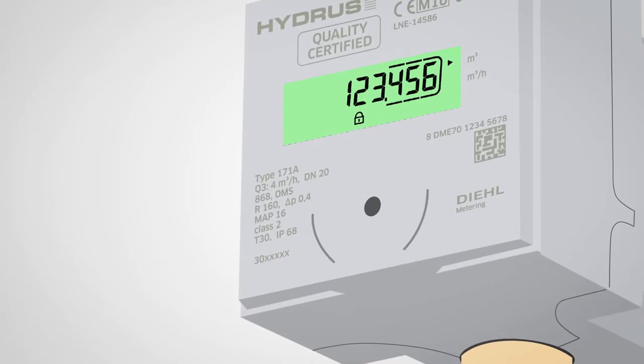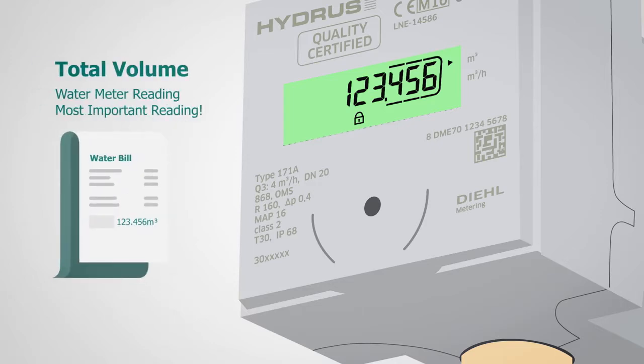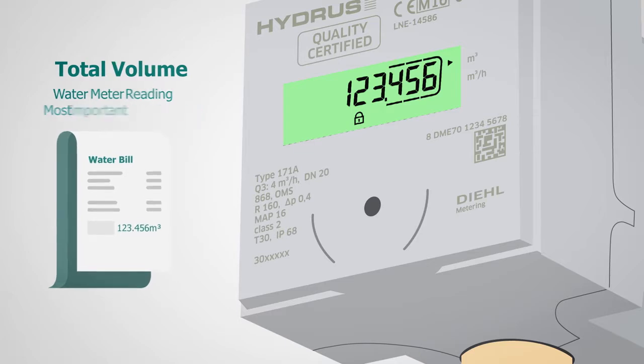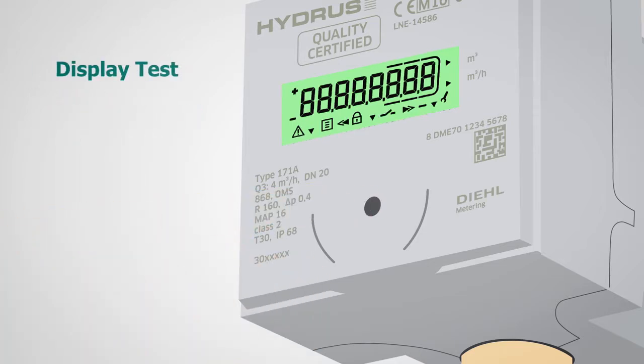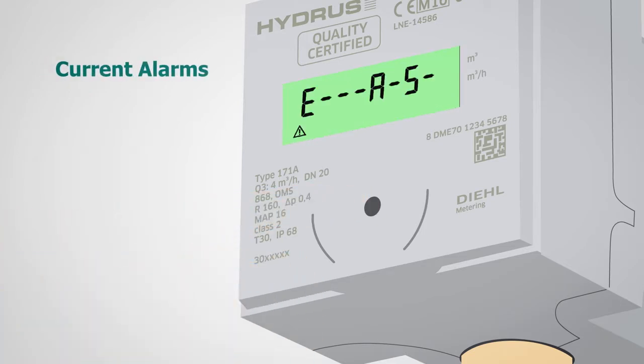Mr. Smith gets all the relevant information in various loops: the current meter reading, the total volume (always recognizable by the little padlock and the arrow pointing to cubic meters), display test, display on and display off, current alarm notifications, and current flow of water (the arrow is pointing now to cubic meters per hour).